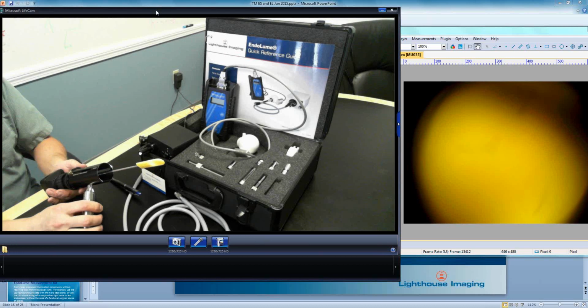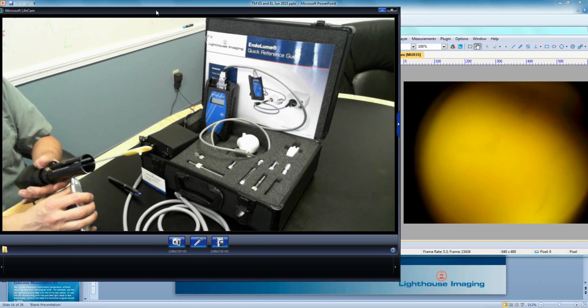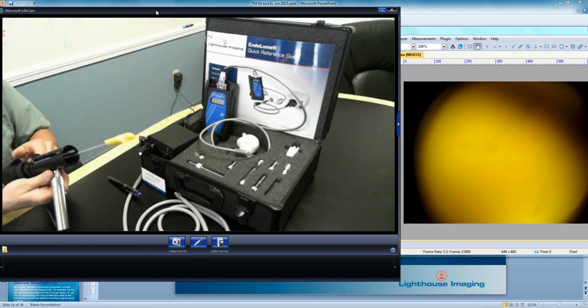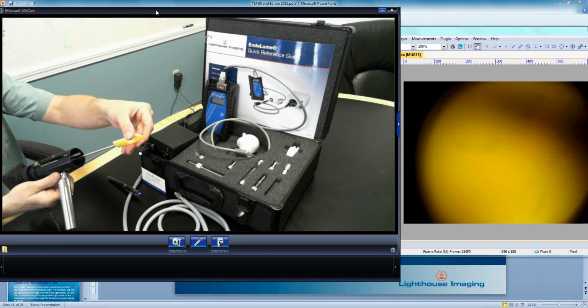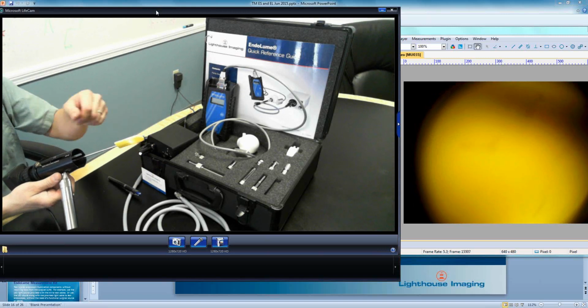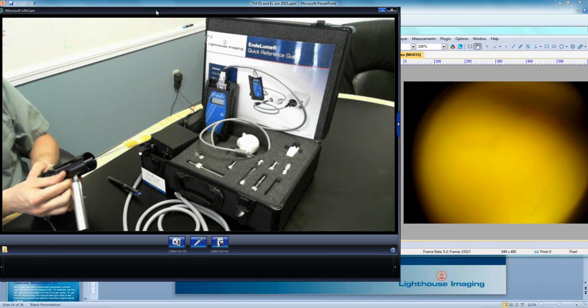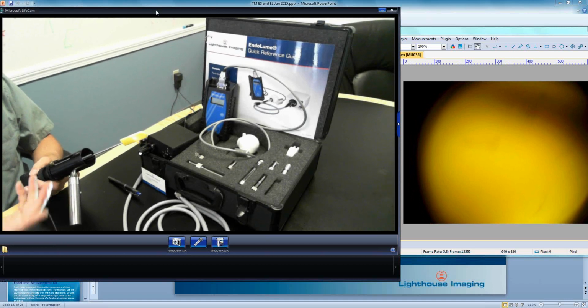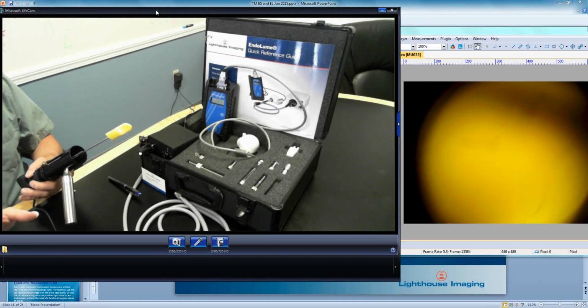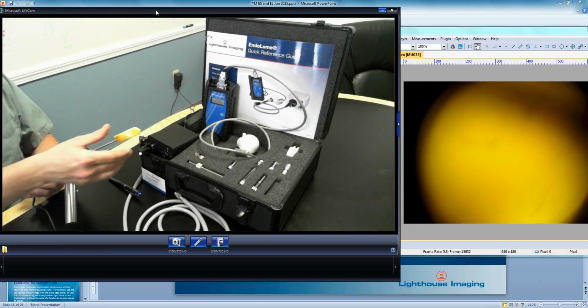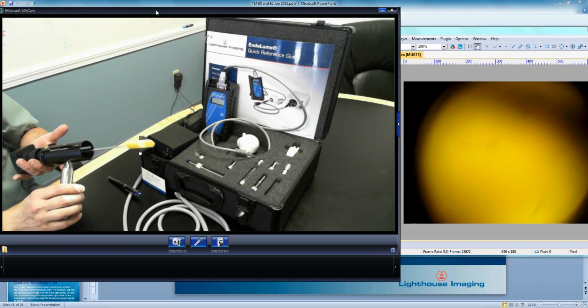So if we look at the small yellow image, what I've done is I have a light source hooked up to it, and this rubber tip I put on the end of the scope gives us a nice even reflection back into the scope. You could do the same thing if just manually looking through this by aiming the scope at, say, a shaded window or a fluorescent overhead light with a diffuser on it. But I just put this clip on it so that I can hold it here in front of you.